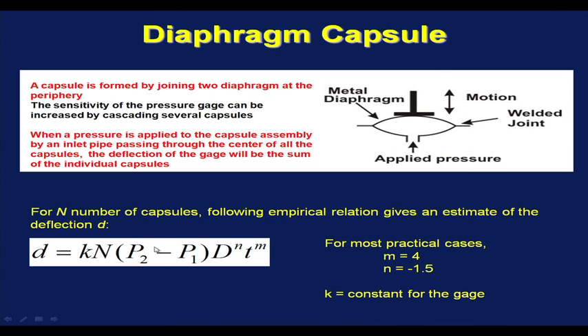This is an empirical relation which gives an estimate of the deflection of the pressure gauge, and it shows that it depends on the number of capsules, the pressure differential, the diameter and the thickness. K is a constant for the gauge. For most practical cases, these exponents m and n are chosen as m equal to 4 and n equal to minus 1.5. So, if we increase the number of capsules, there will be more deflection.